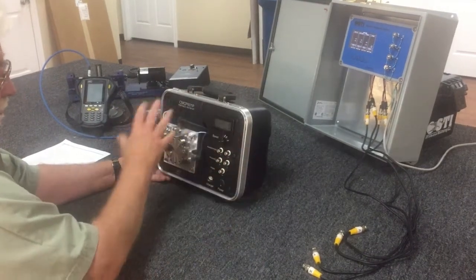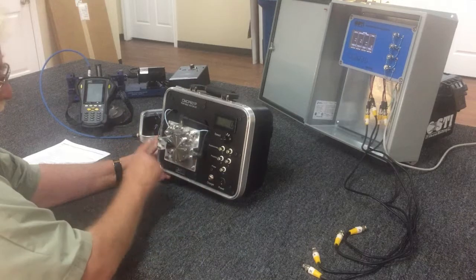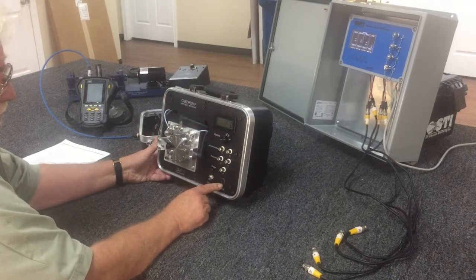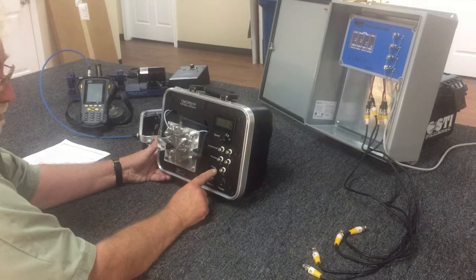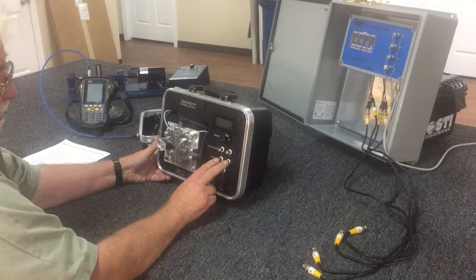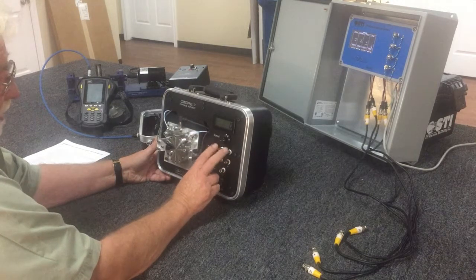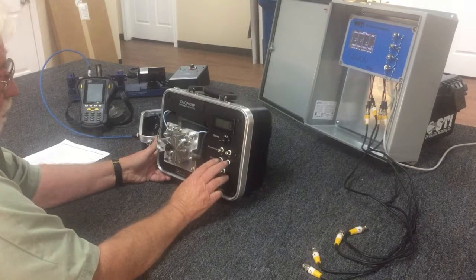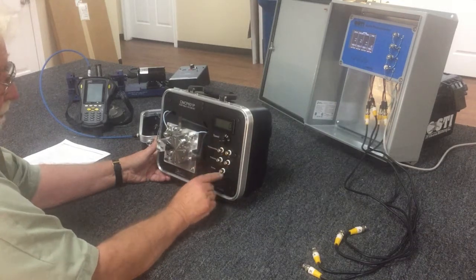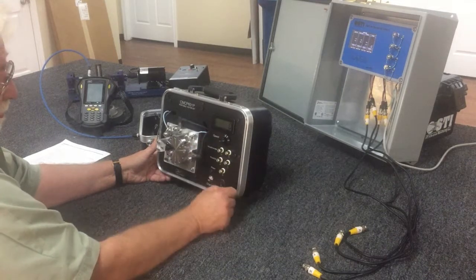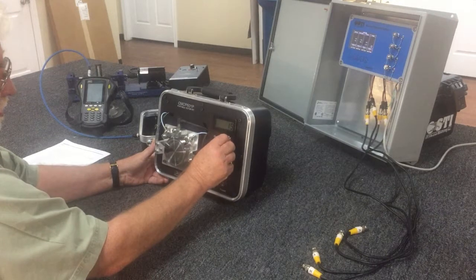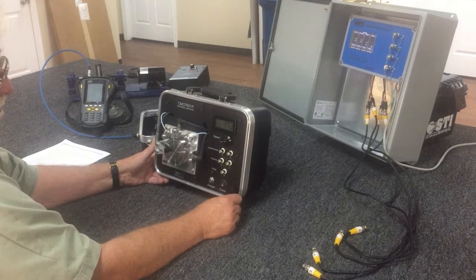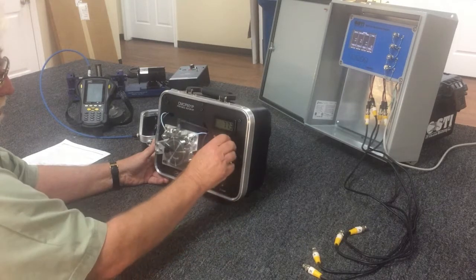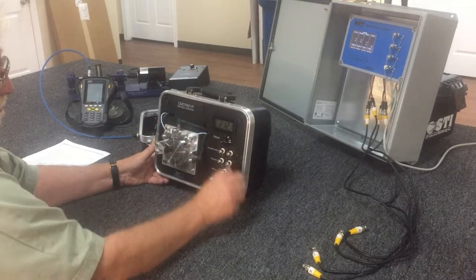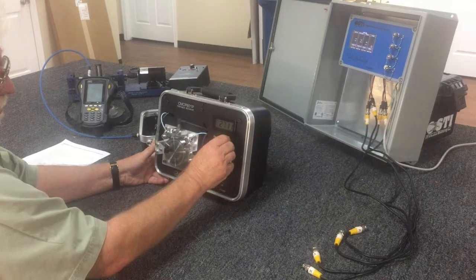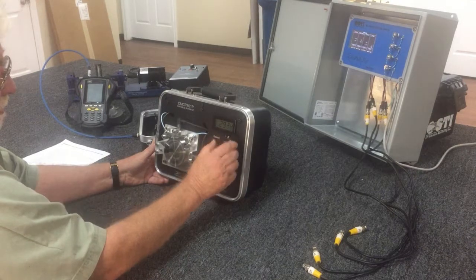All right, let's go through the front faceplate. What we have is a charger port to plug the smart charger into. We have an off-on power switch. We have 5 BNC connectors, 1 for phase. We have 2 for proximity, X and Y, and we have 2 for accelerometers, V and H, vertical and horizontal. But you can wire these however you want them. You could have 4 accelerometers, you could have 4 proximity probes, and a phase sensor. You have a speed control, so when you turn the unit on, you can adjust the speed. Currently running at 770. You can run it up to, say, 3600 RPM, whatever you want.